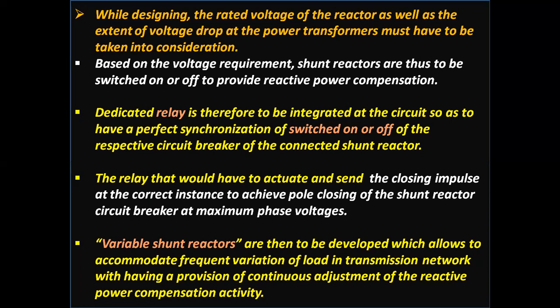A dedicated relay is therefore to be integrated in the circuit so as to have perfect synchronization of switching on or off of the respective circuit breaker of the connected shunt reactor. The relay has to actuate and send the closing impulse at the correct instant to achieve pole closing of the shunt reactor circuit breaker at maximum phase voltages.